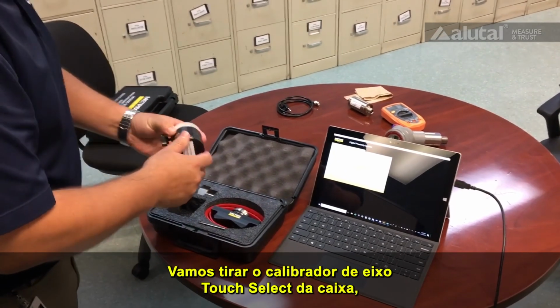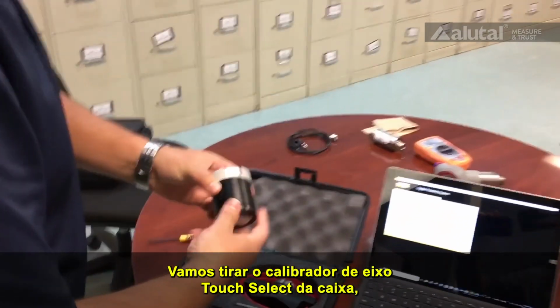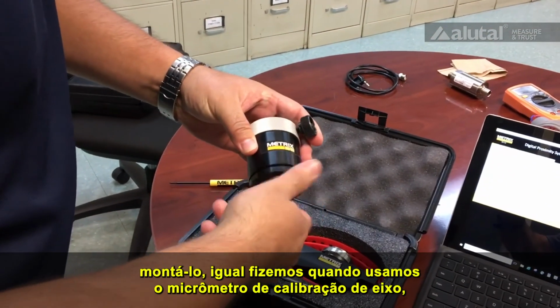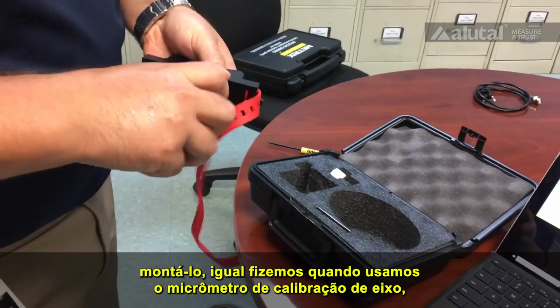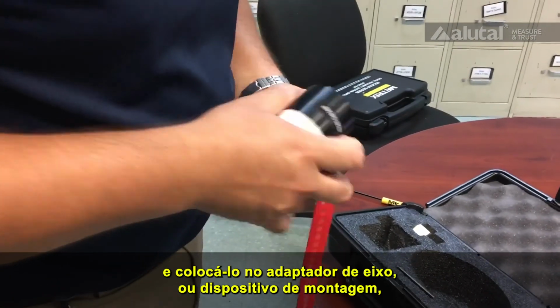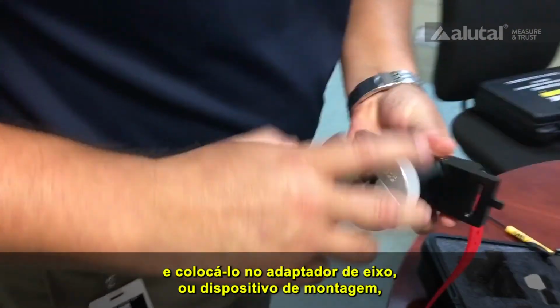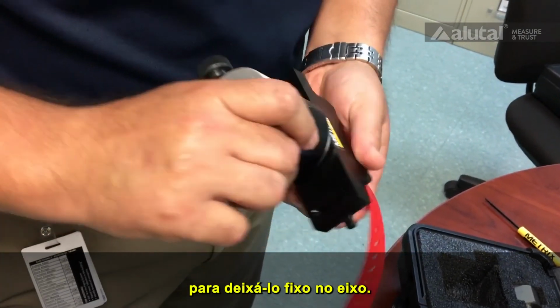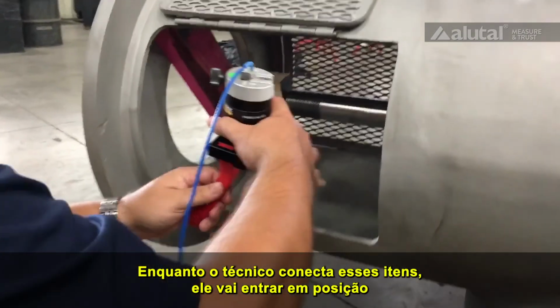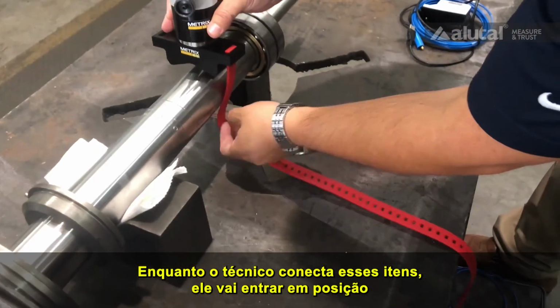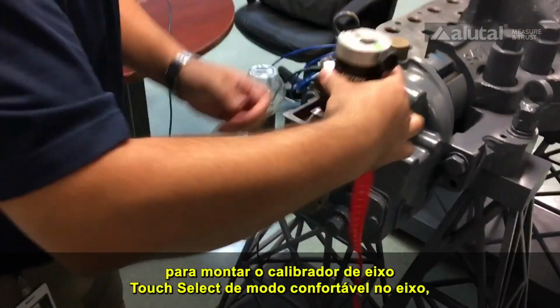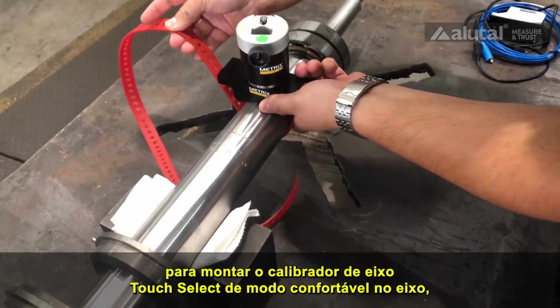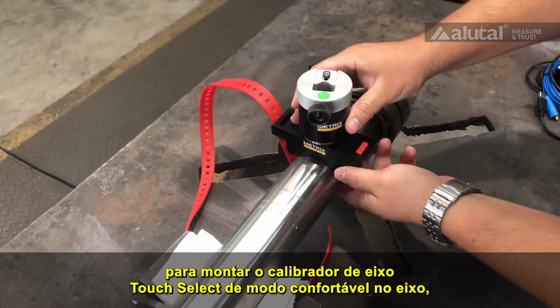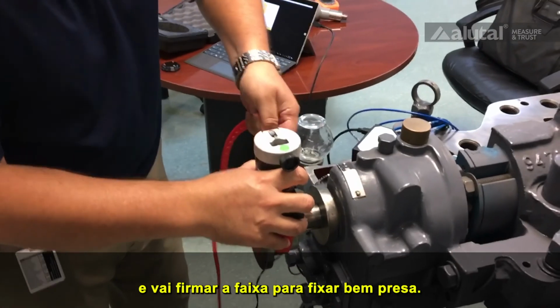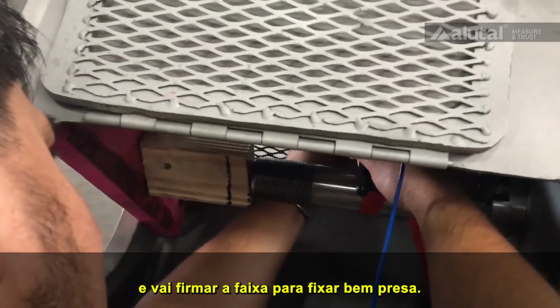On site, we do the same thing that we did in the classroom. We'll remove the shaft calibrator touch select from its case. We'll assemble it just like we did, where we took the shaft calibration micrometer and put it onto the shaft calibration cradle or mounting fixture, so that we can fix it to the shaft. As the technician puts those items together, he'll then move into position so he can comfortably place the shaft calibrator touch select onto the shaft, and he tightens up the strap so that it's secure.